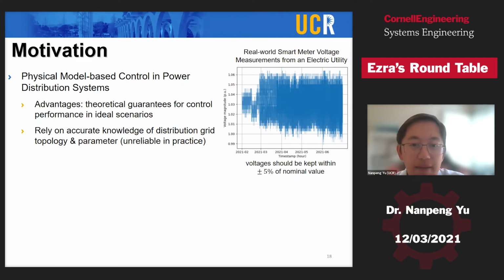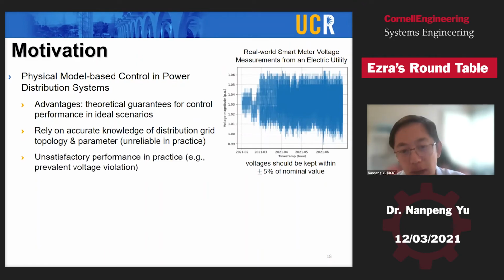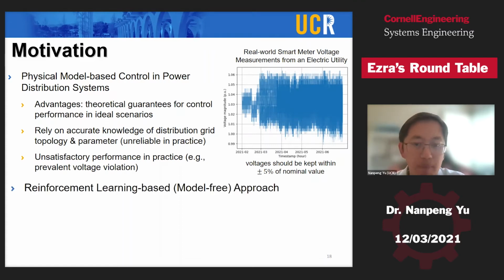However, in practice, this information is often unavailable. Therefore, when people try to apply this model-based control, they often obtain unsatisfactory performance. For example, the figure on the right shows you the real-world smart meter voltage measurements for a regional electric utility. These are the per unit voltage magnitude. And normally, we want the voltage magnitude to be between 0.95 and 1.05. But on this particular circuit with very high solar PV penetration, we can see that we have prevalent overvoltage where the voltage even goes beyond 1.06 per unit. And this is a problem that many utilities observe.